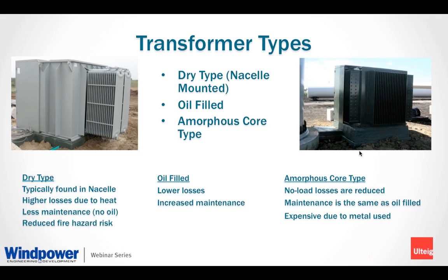So, transformer types. There are a lot of different types of transformers. I'm going to touch on a few that are very common to the wind farm industry. Dry type transformers are usually provided by the turbine manufacturer because they're put inside the nacelle that's up on top of the tower. These tend to be beneficial because the power is immediately transformed to the higher voltage, like the 35 kV, and that 35 kV runs down the tower and out to the collection system. This particular voltage actually helps decrease losses. The only issue is that dry type transformers tend to be a little bit more lossy, so there's a little give and take on which particular transformer is actually better when you consider the different types.